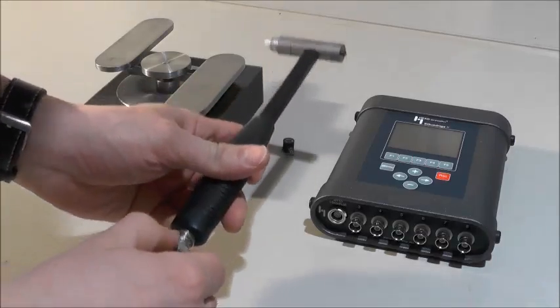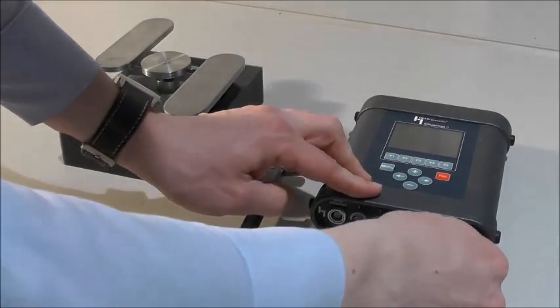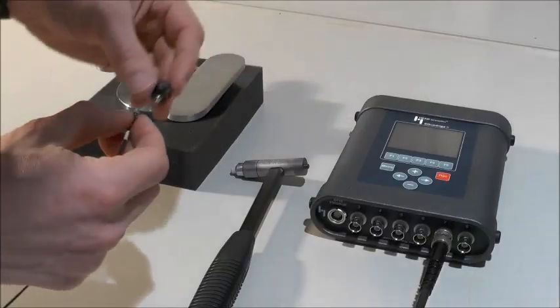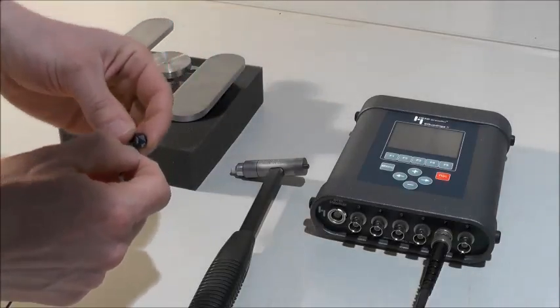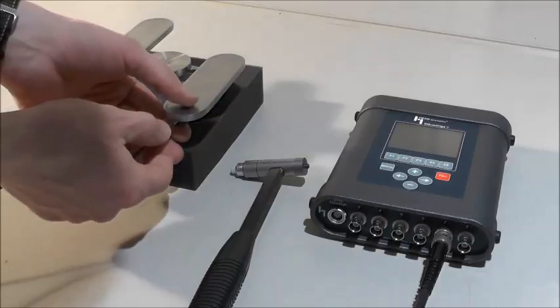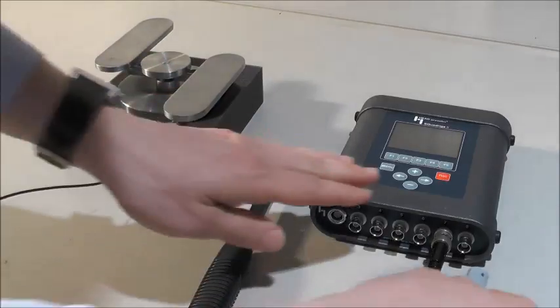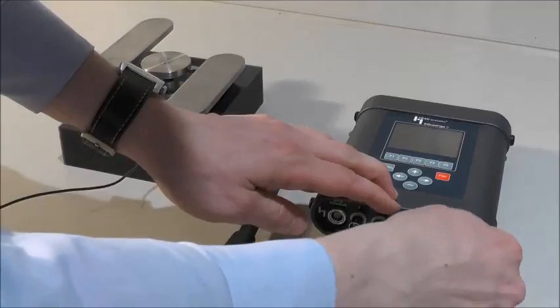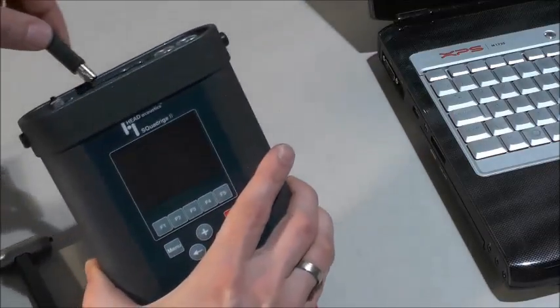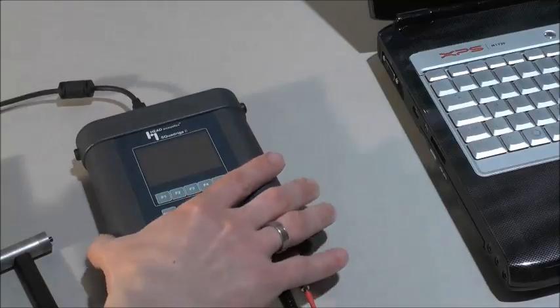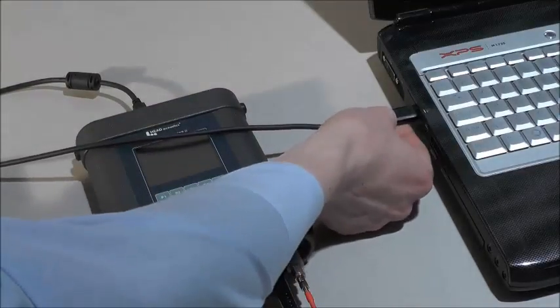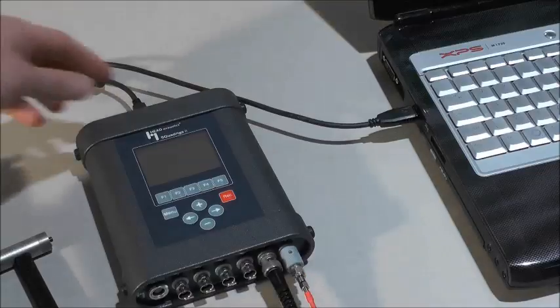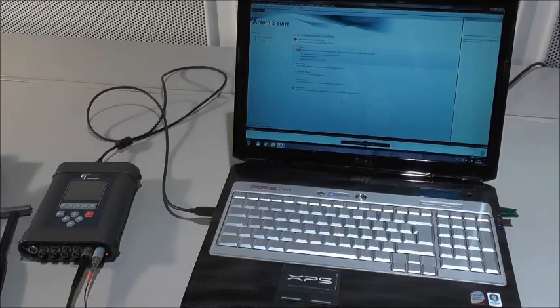We connect the impulse hammer to our front-end, in this example we use channel number 7. We also connect the accelerometer, stick it to a fixed point on our test object, and connect its output signal to channel number 8. We connect the front-end to our computer via USB and switch it on. Our measuring setup is ready.